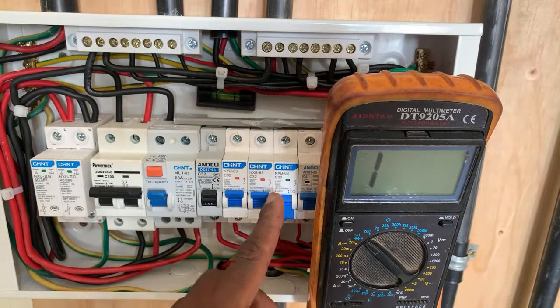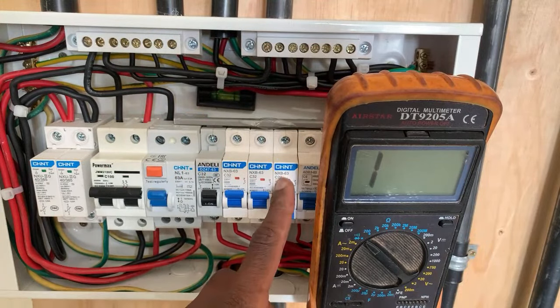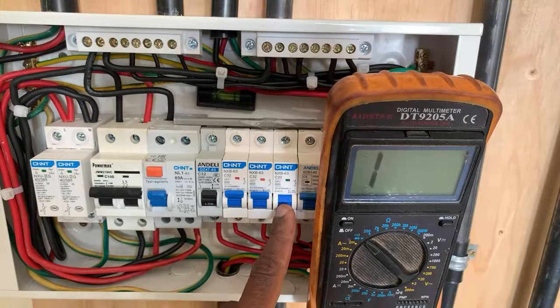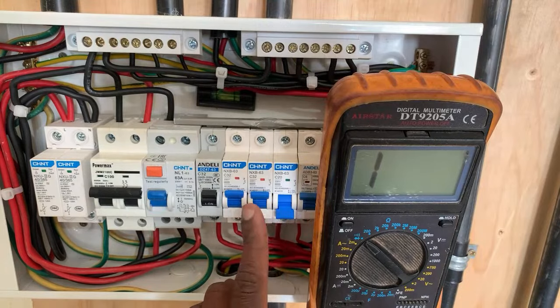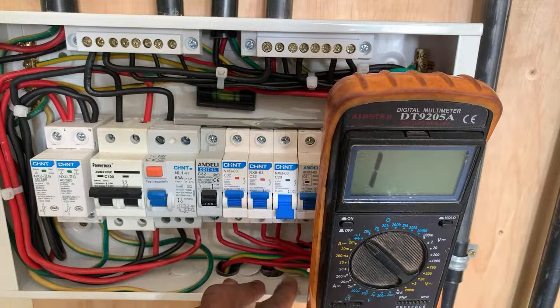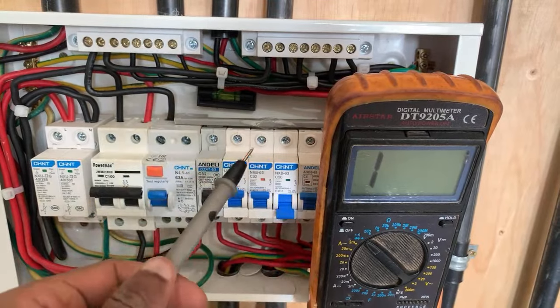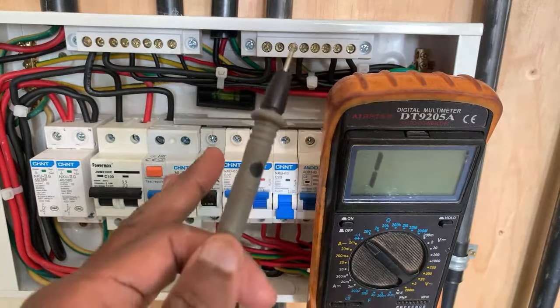If this is a pump or a socket, for instance, on a 20 amp MCB, you need to know that it is connected to a pump. If that pump is not powering on, then that is the suspect. What you need to do is to disconnect that pump. Once you have disconnected it, you will still come here and do the troubleshooting on the pump. If the pump is the one that has a short circuit, then that is the issue.